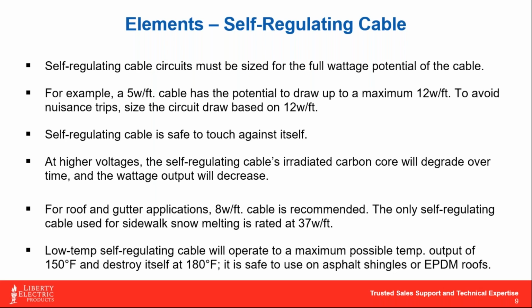A 5 watt a foot cable, let's say, for example, has a potential to draw up to 12 watts a foot at full output. So if that thing was encased in snow and ice and the system was not on automatic controls and somebody flipped a switch on, that cable is going to have a millisecond inrush current at 12 watts a foot. So we have to size our electrical circuit based off of that. So when we're doing this calculation, again, we typically use 30 amp 2-pole breakers, for any of you electrical folks out there. And because we cannot exceed 80% rated duty of the breaker, we have to be careful as to how many feet of heat cable we can put on that circuit.